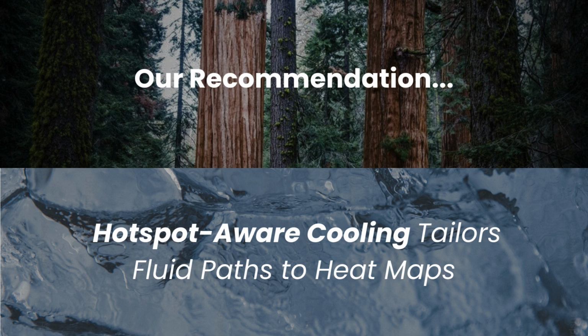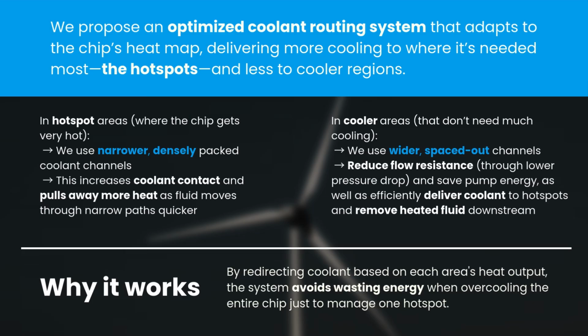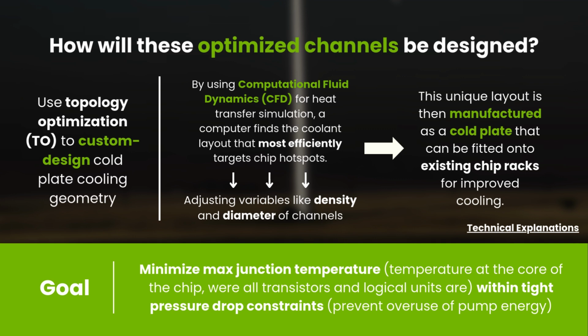This inefficiency hampers system performance, prompting a need for effective solutions. Our recommendation is simple: hotspot-aware cooling that is optimized to match heat maps. To put it simply, we route the coolant based on where the heat is. In hotspots, we use dense, narrow channels to maximize heat transfer. In cooler zones, channels are wider and spaced out, reducing resistance and pump energy. This system adapts to the chip's heat profile and efficiently cools where it matters most, lowering both power usage and thermal throttling.